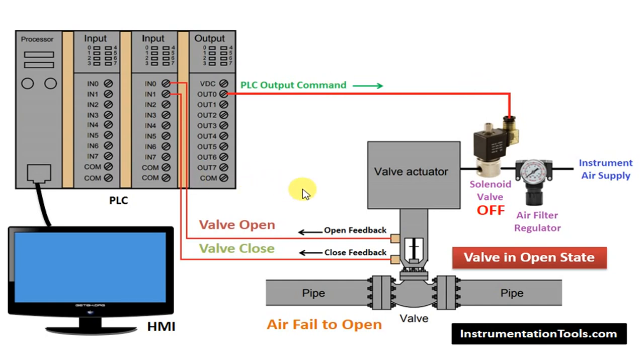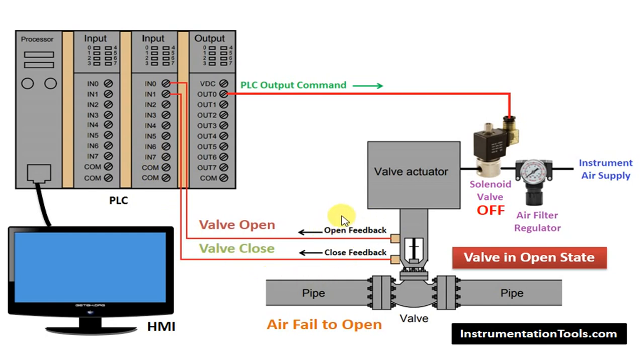First, we discuss our default condition. We have instrument air supply available here, and the SOV — solenoid valve — is in off condition, and the valve is in open state. Every on-off valve has two proximity switches: one for open state, and second for closed state. When the valve is in closed condition, the close proximity switch sends a signal to the PLC. When the valve is in open state, the open proximity switch sends a signal to the PLC.